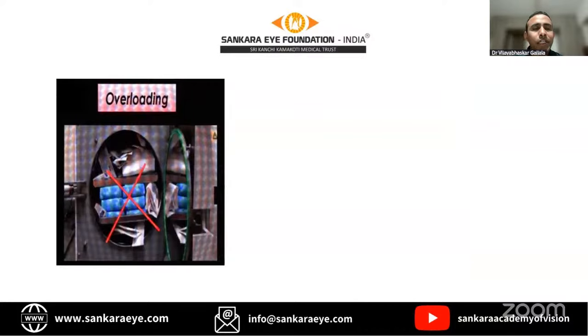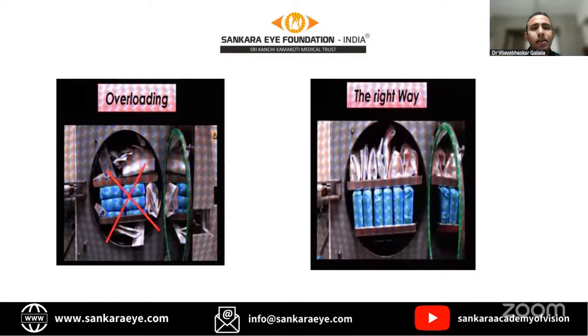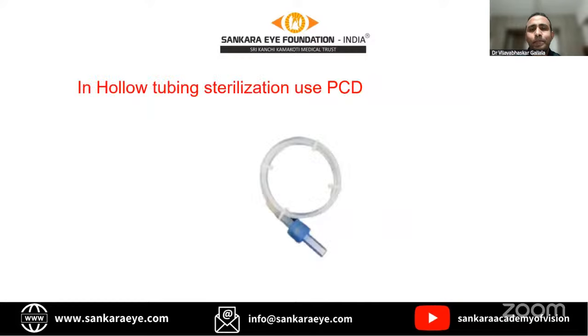So what are the things that we need to keep in our mind regarding autoclave sterilization is we should not overload this chamber with multiple sterilization sets. And this is the right way. So always keep the heavy load down and lighter load up with proper spacing between these loads, which allows the steam to penetrate through all the packs.